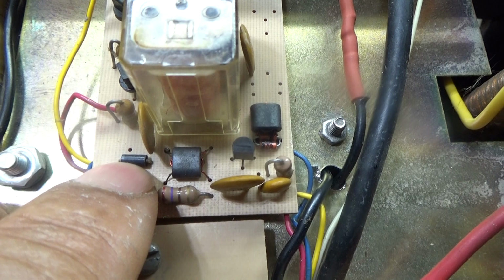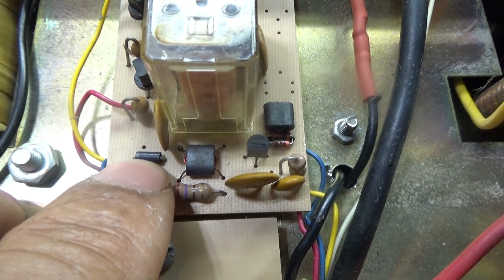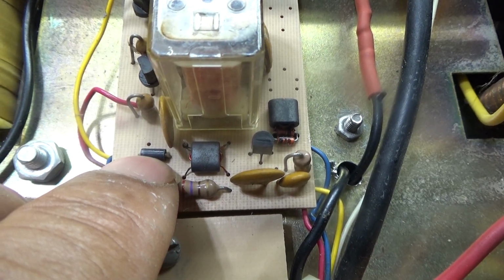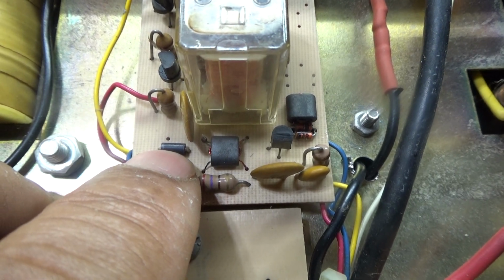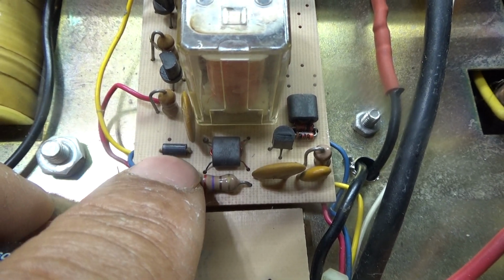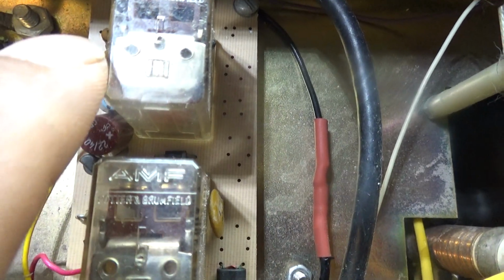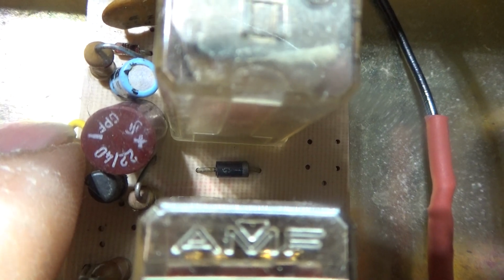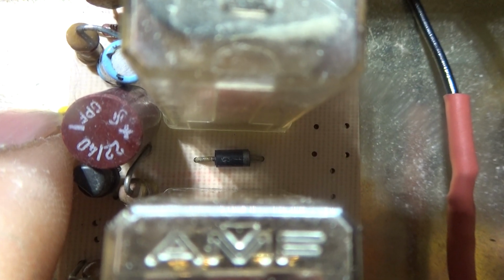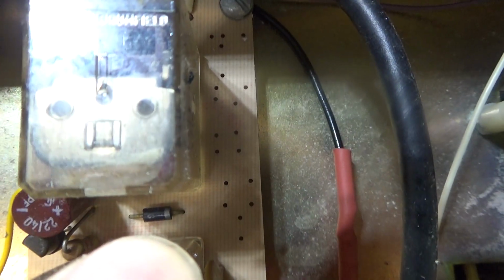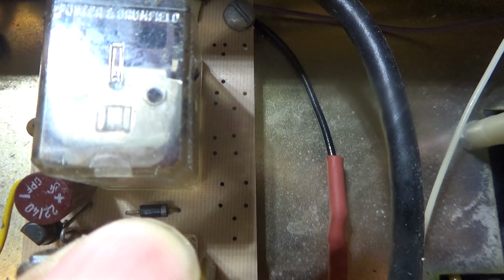Normally these don't go bad, but if you think one is bad, pull a lead out and test it out of circuit like you normally would. You have to pull a lead off these diodes, since they go across the coil of the relay. They're anti-chatter diodes across the coil, so you can't read them in circuit, they'll show a short because you're reading the coil they're connected to, not the diodes. So you've got to pull them out to read them.